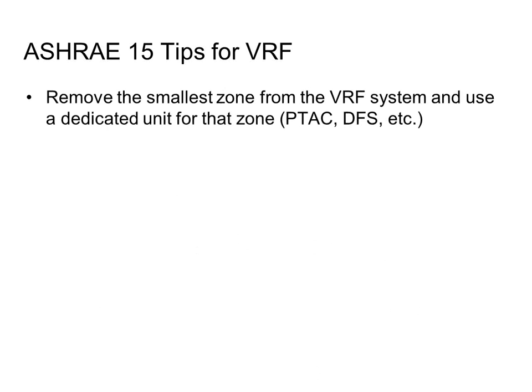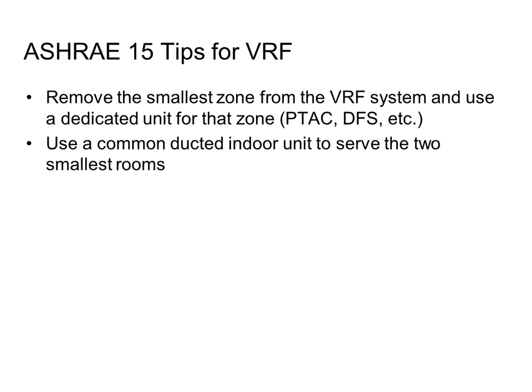The first thing you can do if you can't meet the 25 pounds per 1,000 cubic feet for one of your zones is get rid of the smallest zone. Right? I'm not saying get rid of the zone in the building, but take it off the VRF system. If you've got this VRF system and all the zones are big and you've got this one little tiny rogue zone on its own, take it off the VRF. Put it on its own split system or ductless split or something like that, and get it out of the calculation. And then go look at your next small zone. Now, if you've got a bunch of small zones, like a dormitory building, that's not going to work. But if you only have one or two rogue small zones, this is a solution.